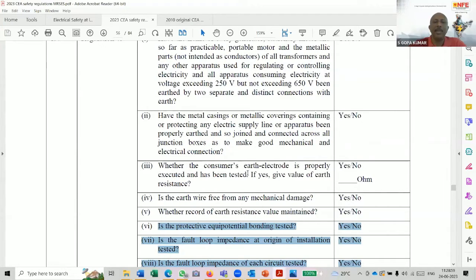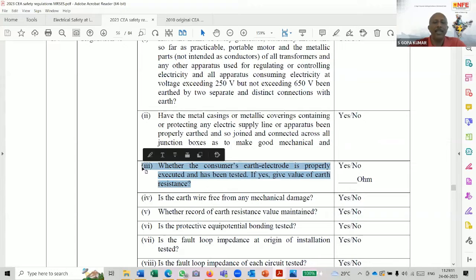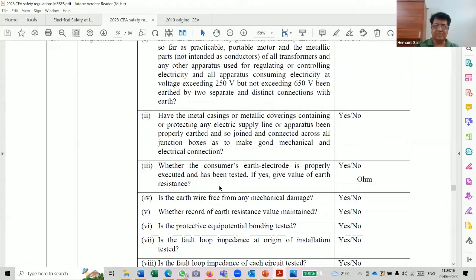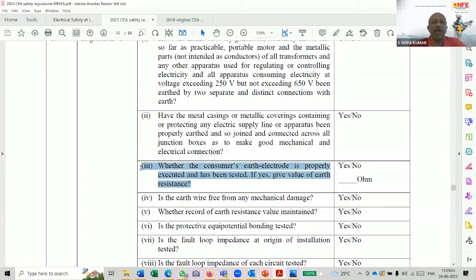But now you see, for example, this one where I'm highlighting: whether the consumer's earth electrode is properly executed and has been tested. If yes, give the value of earth resistance. This is applicable only in the case of a low voltage consumer premise. Imagine the supply voltage is high voltage and it is converted with a transformer, and the LV is used within the consumer premise. People may try to misinterpret it. They will still ask, where is the earth electrode resistance value? This is actually to substantiate regulation 18.